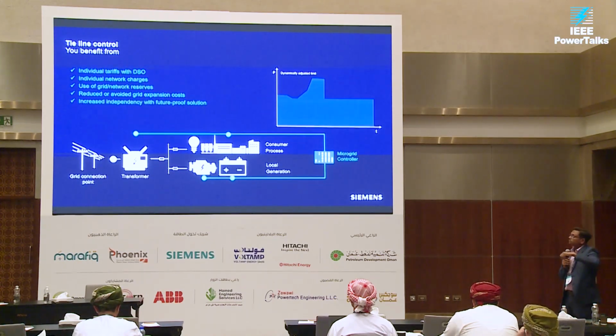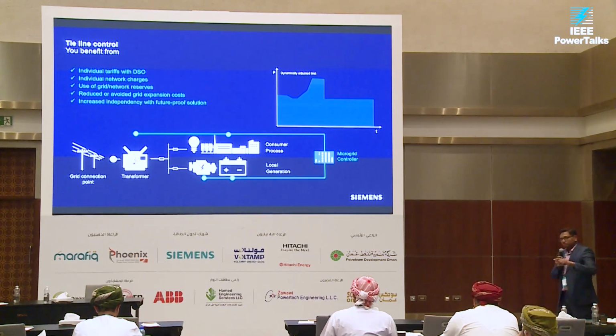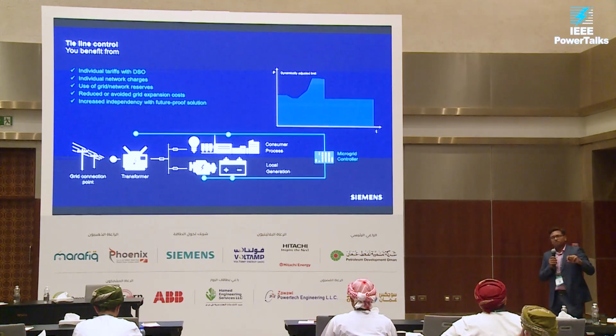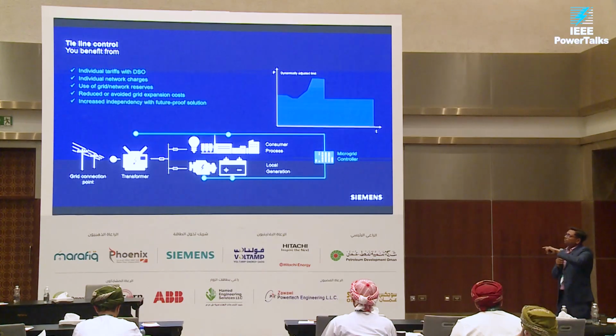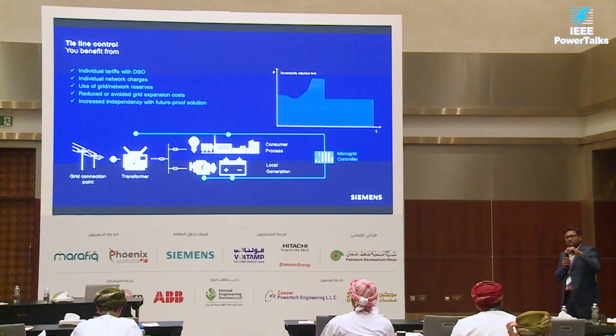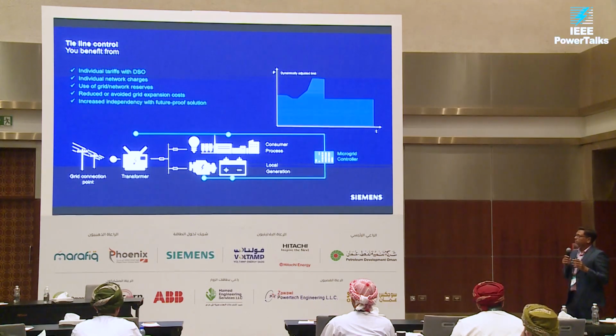And the good thing is the power generated by the microgrid using the microgrid controller is very stable. So before importing or exporting, it will always check voltage and frequency. If it matches with the traditional grid, then only it will allow. Otherwise, unless the voltage and frequency match, it is not going to close the breaker between traditional grid and microgrid. So that is very stable power.